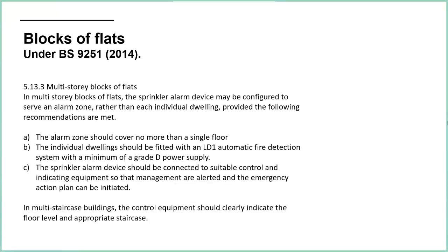Okay, so I'm going to stop quite a few times reading this just to point out a few things. For me, this sentence is saying you've got two options. You either have one sprinkler alarm device per dwelling, per apartment, per flat, whatever you want to call it, or you have one per floor with the following conditions. Having one alarm for the whole building, no, that's not compliant with the code. So you've got a choice of either one per apartment or one per floor. If you're going for one per floor, then you need to follow the following conditions. So no alarm zones cover more than one single floor.